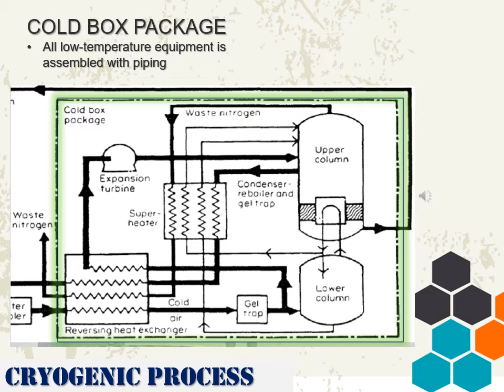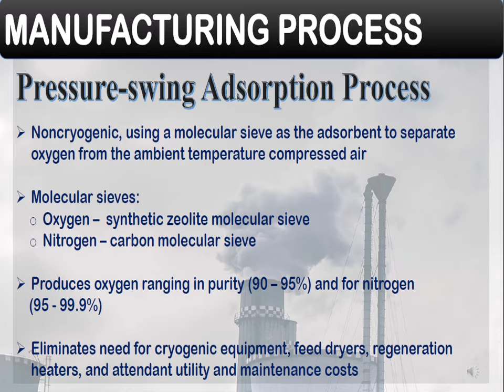Some oxygen is produced by a non-cryogenic pressure swing adsorption process using a molecular sieve as the adsorbent to separate oxygen from ambient temperature compressed air. This process produces oxygen ranging in purity from 90 to 95% and 95 to 99.9% for nitrogen. This simple process eliminates the need for cryogenic equipment, feed dryers, regeneration heaters, and attendant utility and maintenance cost.